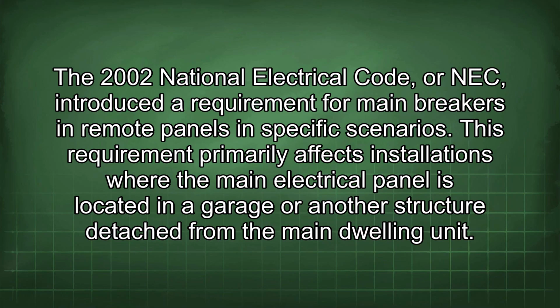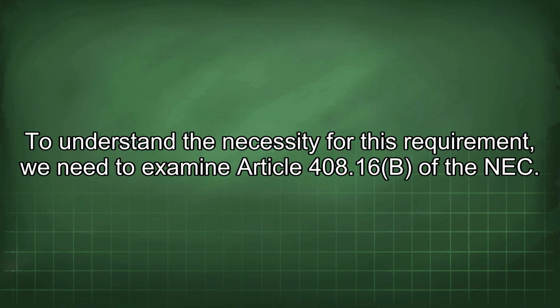The 2002 National Electrical Code, or NEC, introduced a requirement for main breakers in remote panels in specific scenarios. This requirement primarily affects installations where the main electrical panel is located in a garage or another structure detached from the main dwelling unit. To understand the necessity for this requirement, we need to examine Article 408.16b of the NEC.